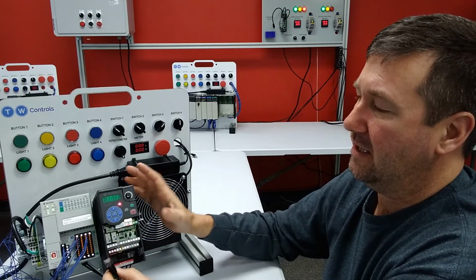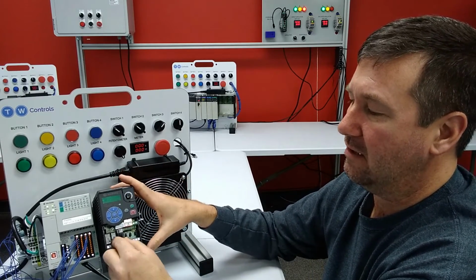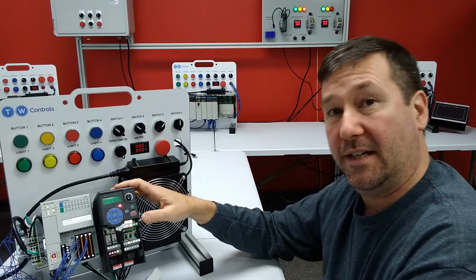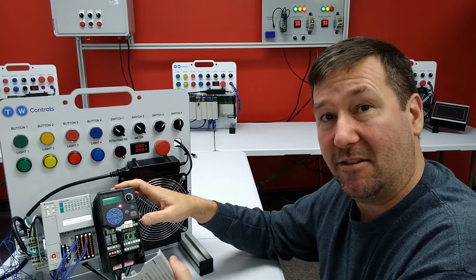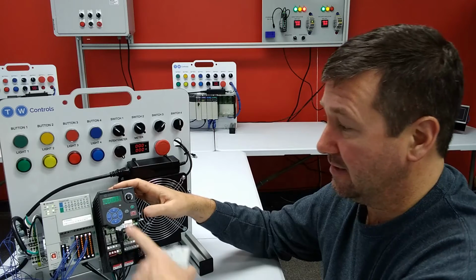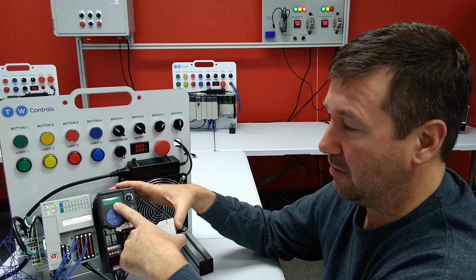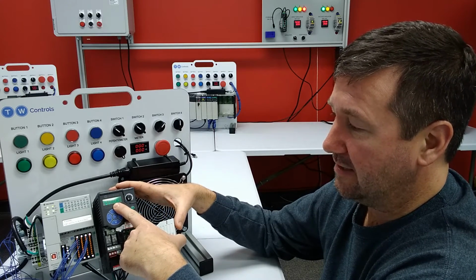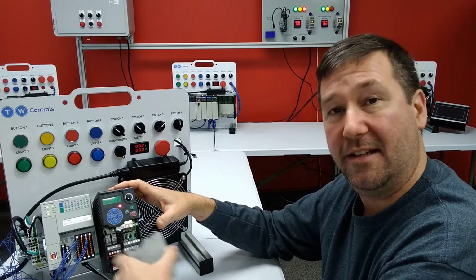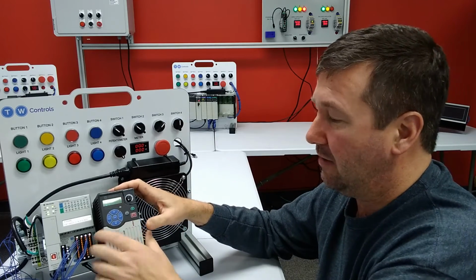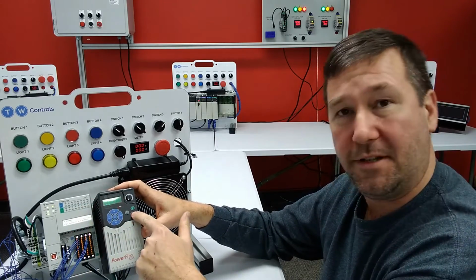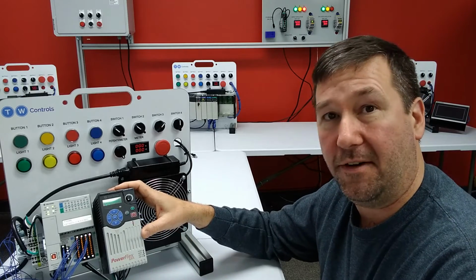Also, one other thing I did there, and I didn't actually tell you what I was doing. Let me unplug mine again. You have a flashing fault light here because it knows that it had an Ethernet connection and something happened to it. And it says right there, F073 EN net loss. And that means, yeah, it's lost its Ethernet connection. What I did is once I had it fixed, I pressed the red button and that clears that fault out.